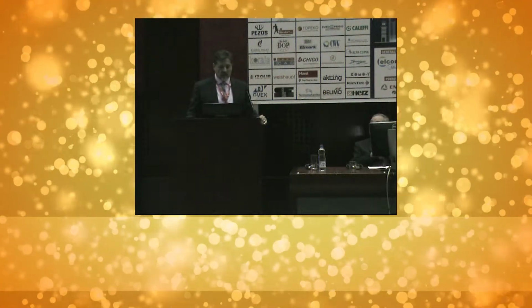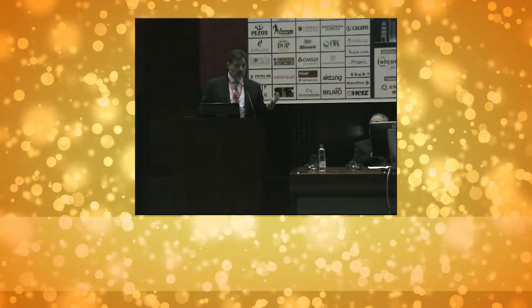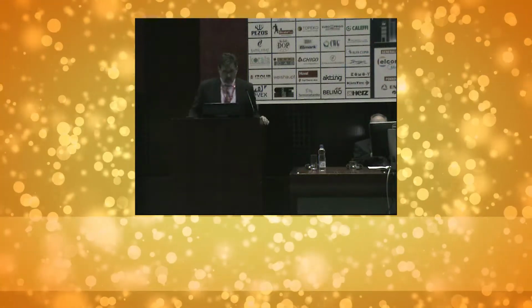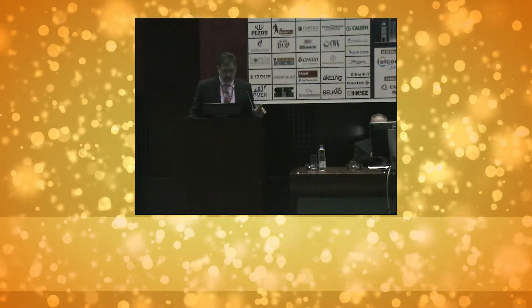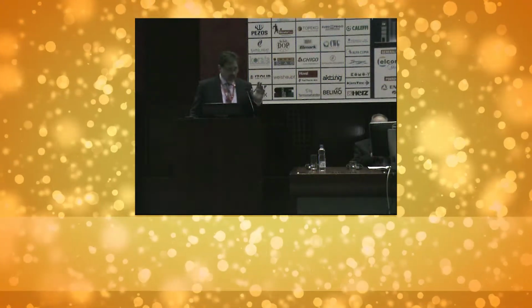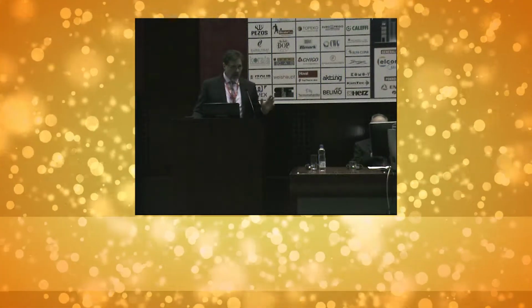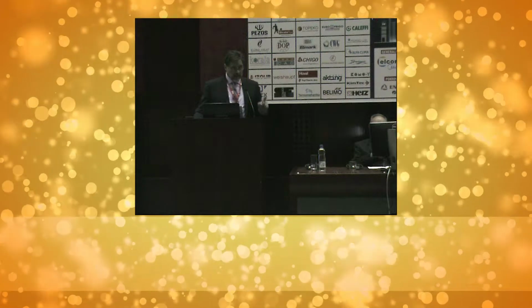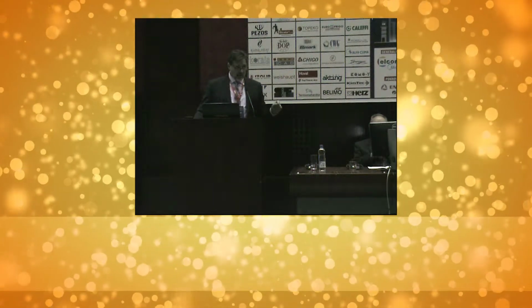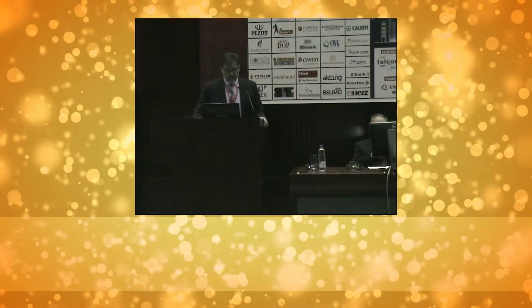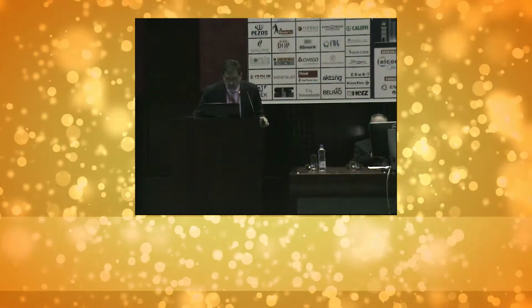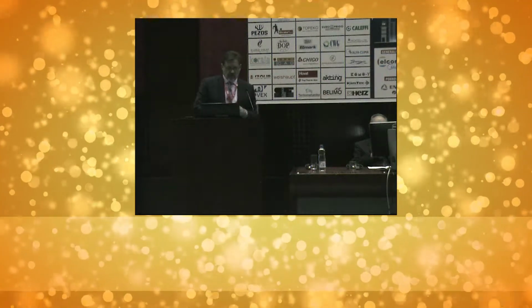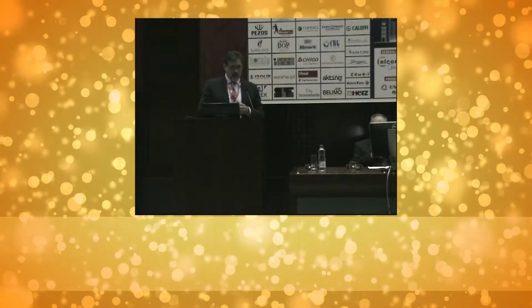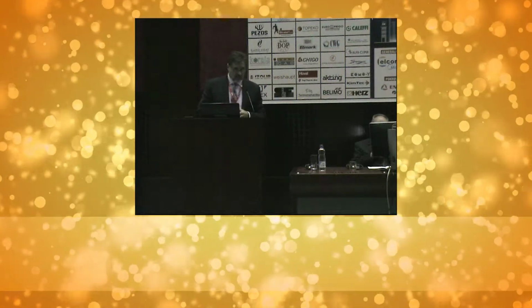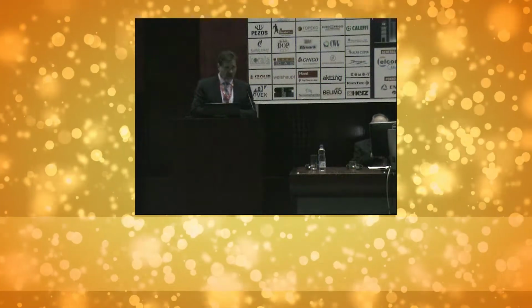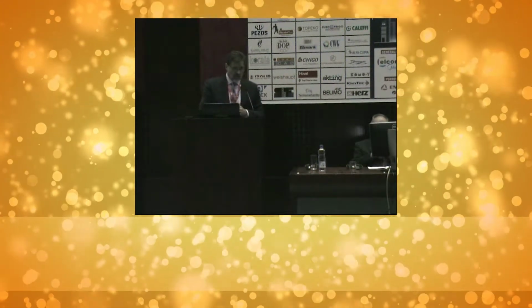So minimum is basically the controllability of that particular box. Controllability is basically the key: how low we can drive that VAV terminal is the answer to how to save energy on it. Controllability really depends on that probe, the airflow station that we use to determine the flow and adjust our flow depending on the needs of the space.